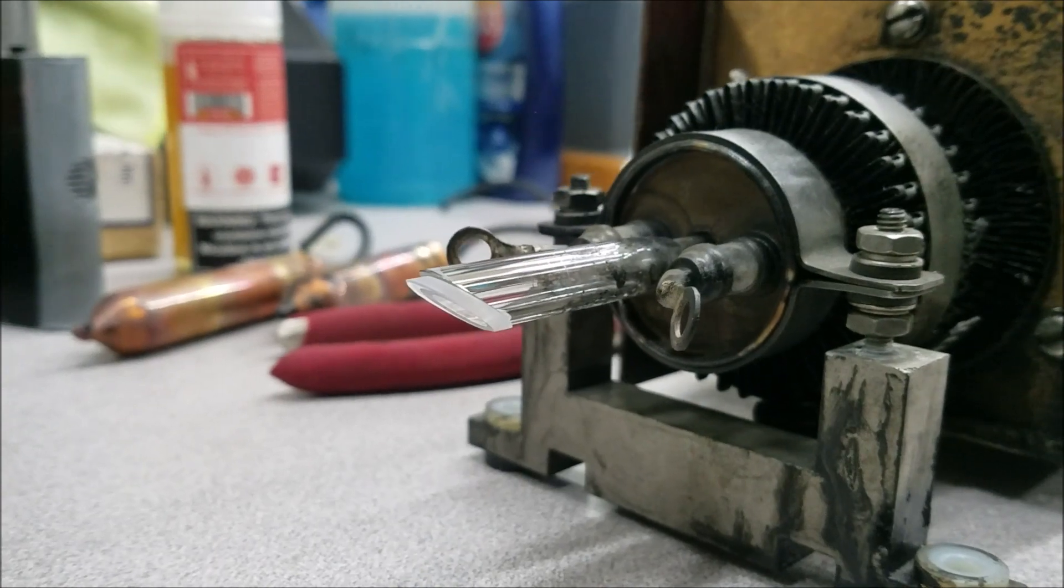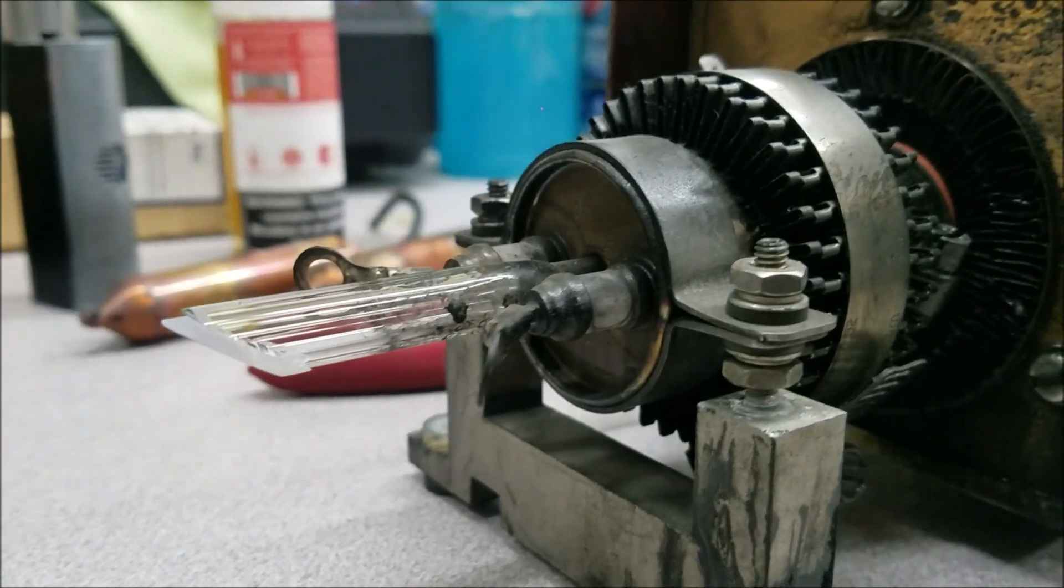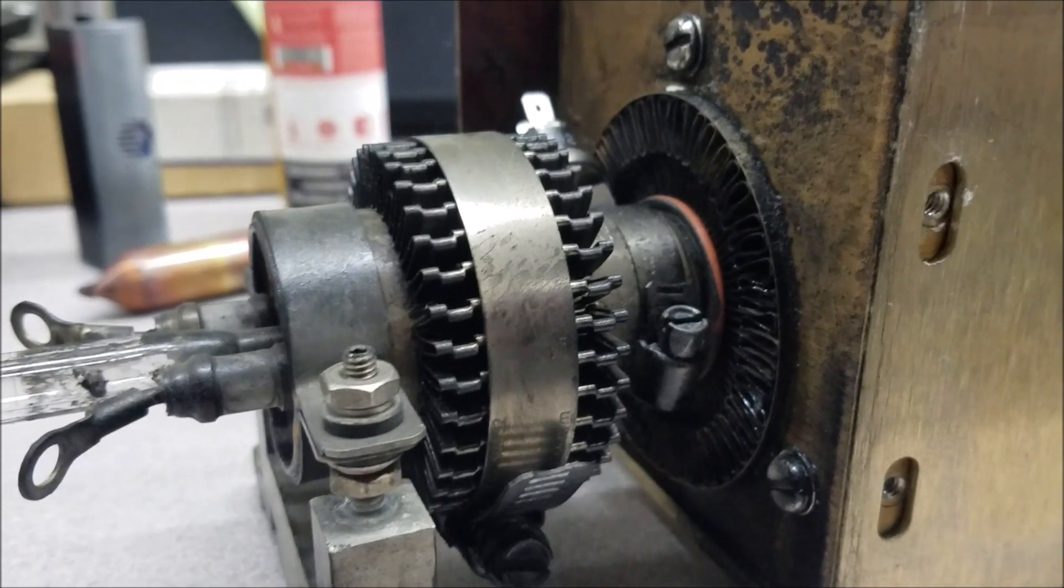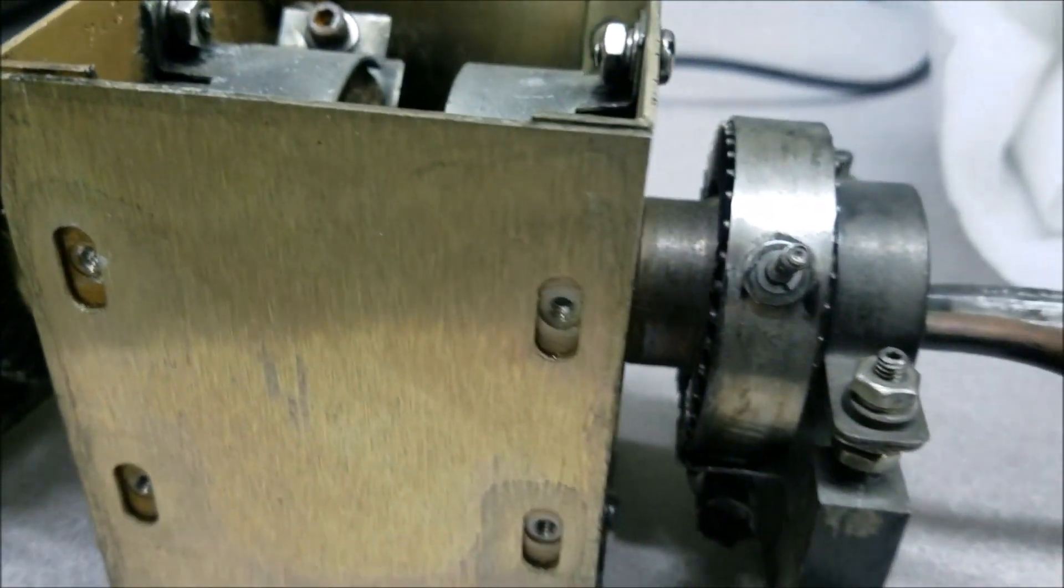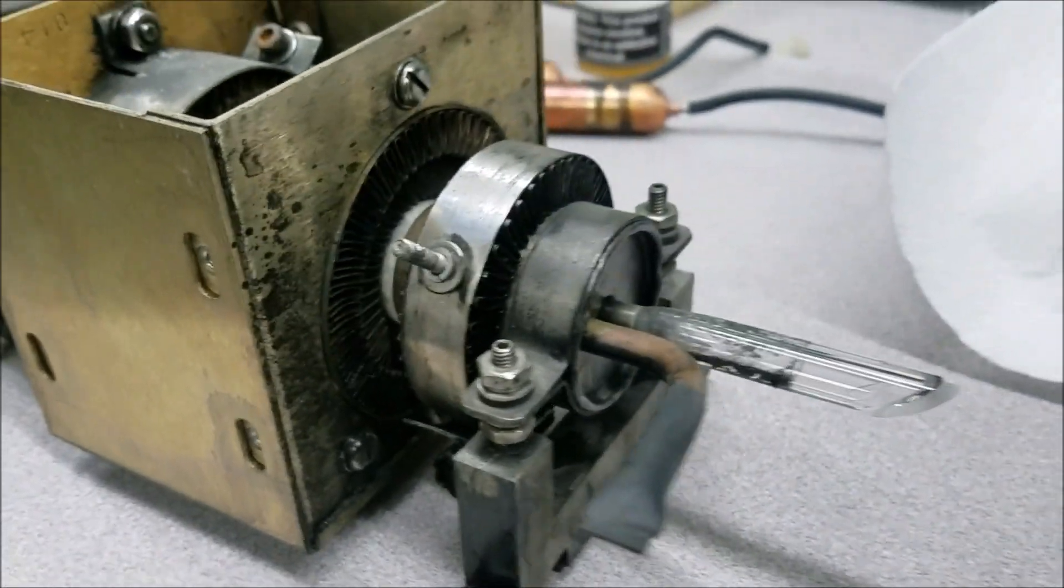This is the laser tube itself. On each end has a specially angled piece of glass called a Brewster window. These are found in most gas lasers as well. Their function is to polarize the light as it travels between a high reflector and output coupler.